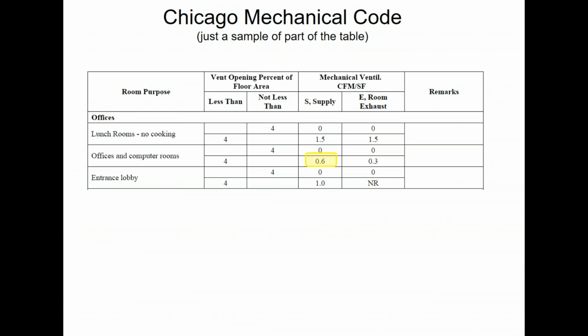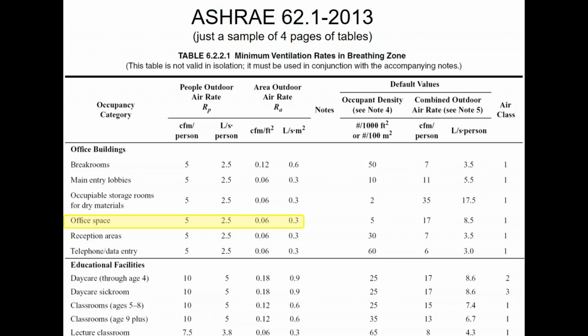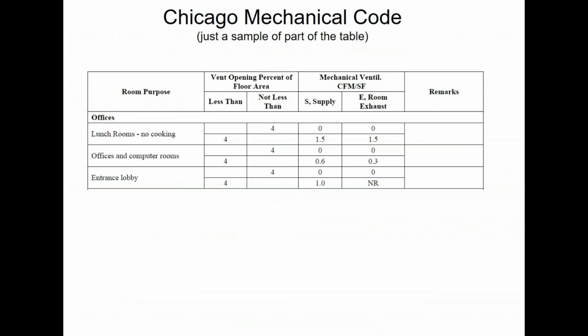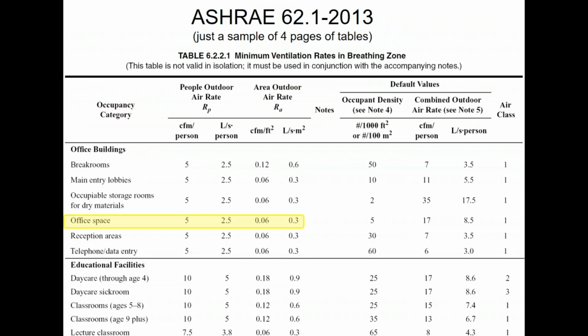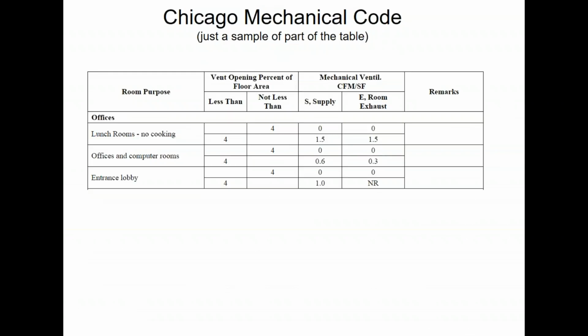You guys are in Chicago, it works completely different. The city of Chicago and the state of Wisconsin are different from like everywhere else. Everybody else that I know of does this. And there's like 4 pages of tables like this for different spaces. Chicago and Wisconsin are different. Wisconsin is simpler. Wisconsin just does 7.5 CFM per person. There's no square footage discussion. There's no 5 CFM, 10, 15. It's always 7.5 for all building types. It ends up being significantly lower than anything that's in these tables up here. But that's how Wisconsin would do it.